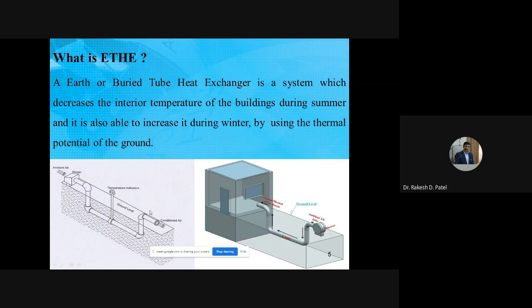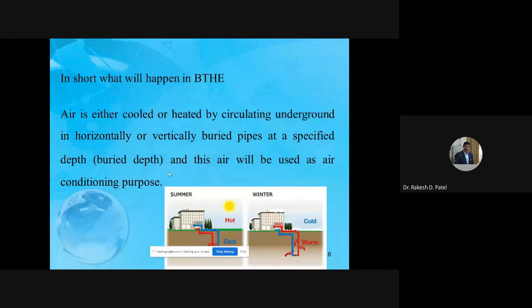This picture clearly shows how heat is exchanged from the buried depth to the room with the help of one simple blower at very low energy consumption. The air is conditioned at buried depth, and this conditioned air is passed to the room or building. In short, the air is either cooled or heated by circulating it underground, in a horizontally or vertically buried pipe at a specific depth, and this specific depth is called the buried depth.